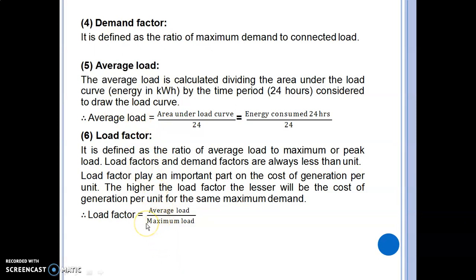The load factor is defined as the ratio of the average load to the maximum or peak load. Both load factor and demand factor are always less than unity. The load factor plays an important part in the cost of generation per unit. The higher the load factor, the lesser will be the cost of generation per unit for the same maximum demand.